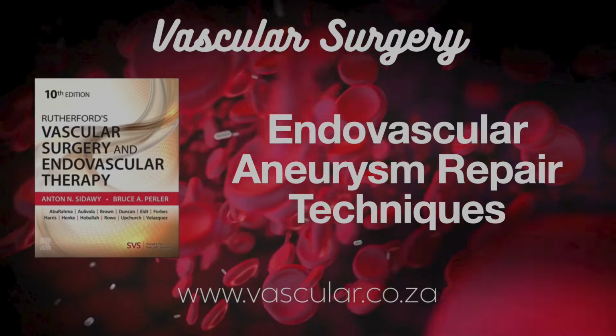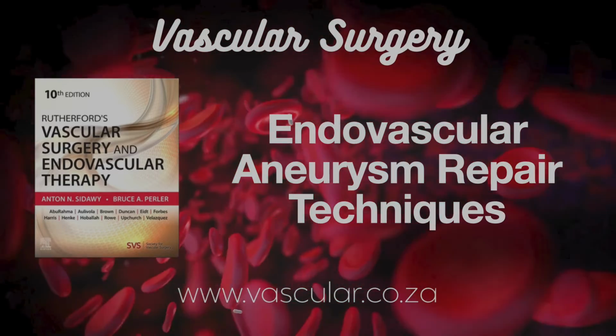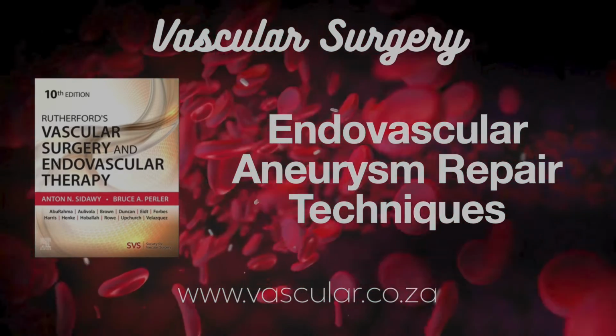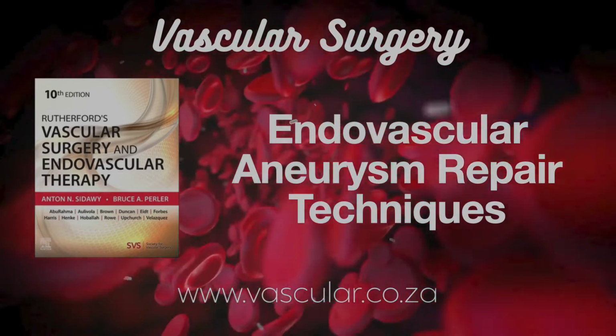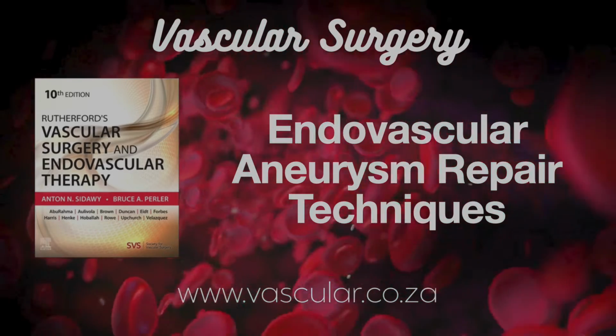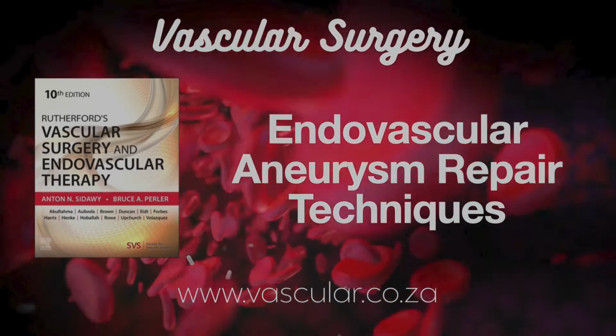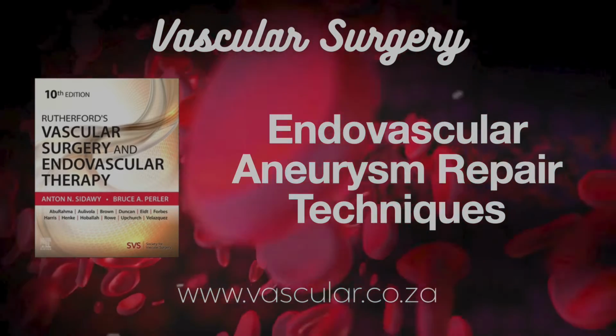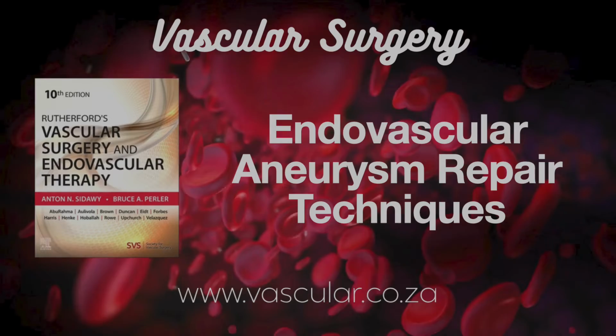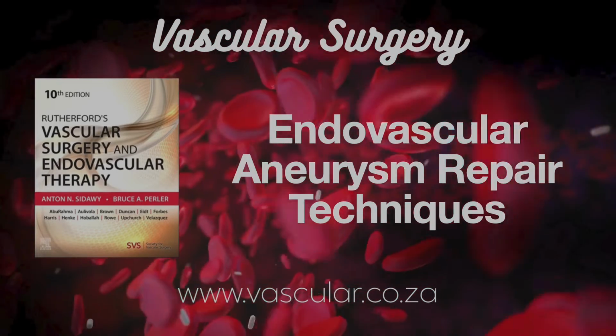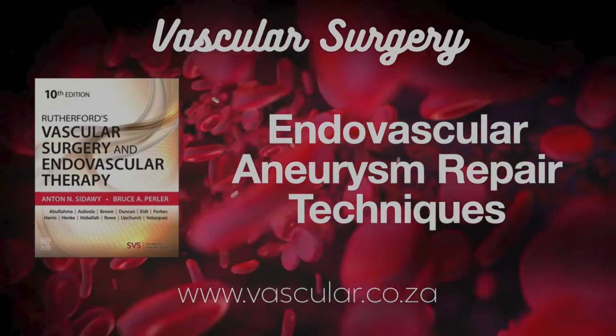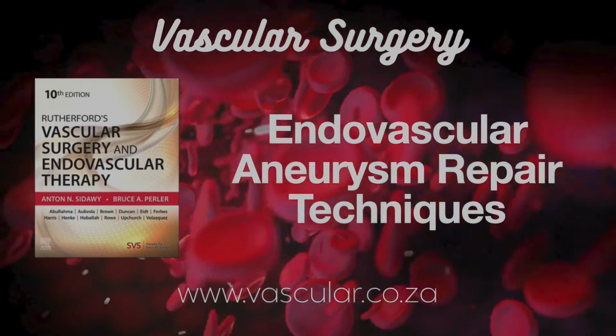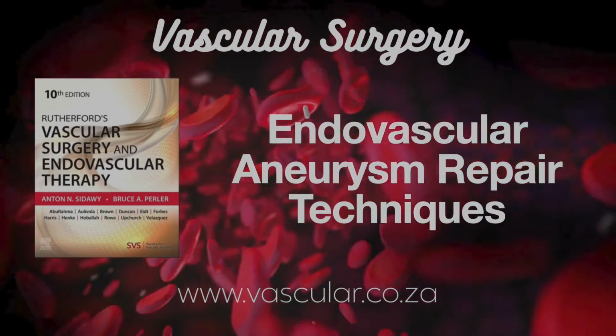Definitely. So once you have the neck diameter, how much bigger should the graft be? Typically oversized by 10% to 20%. Usually means picking a graft diameter 3 to 4 millimeters larger than the measured neck. Devices generally cover necks from about 16 up to 32 millimeters. Why oversize? To get that tight seal against the aorta wall, prevents blood leaking around the top, that type IA endoleak. But you don't want to oversize too much.